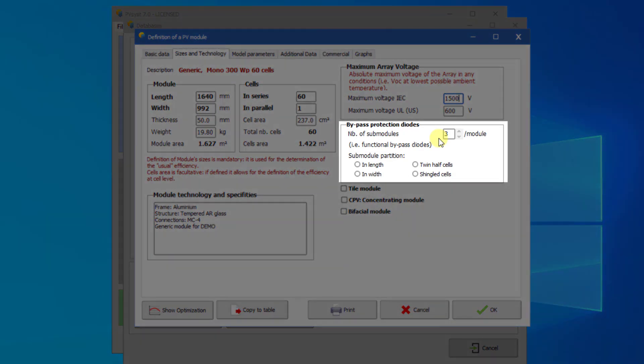In this field, you enter the number of protection bypass diodes. This concerns operational bypass diodes, which define the sub-modules that are used in the module layout tool. Sometimes, manufacturers connect two diodes in parallel, which make six diodes for a standard PV module. In the PAN file, this has to be accounted for as three operational bypass diodes.